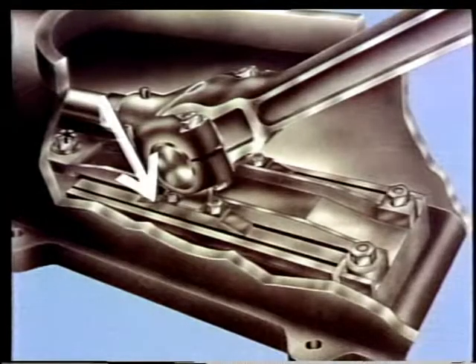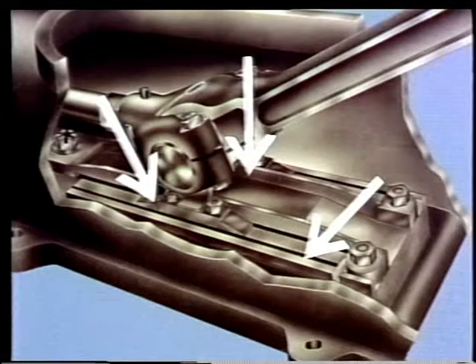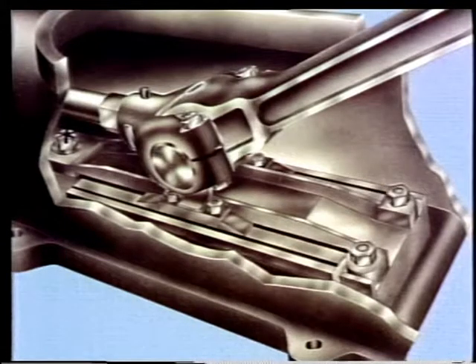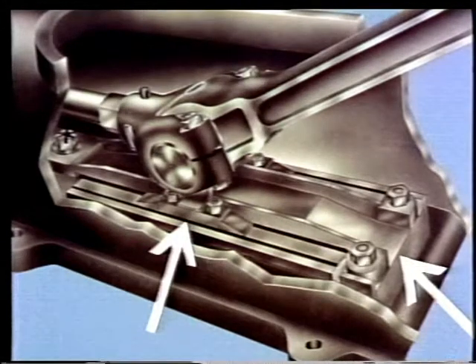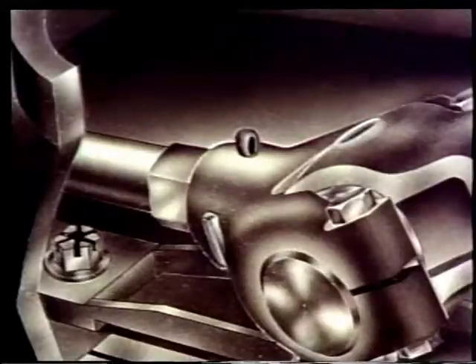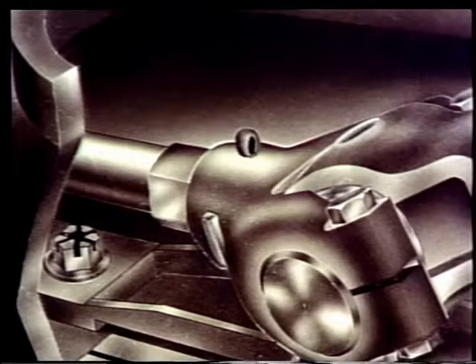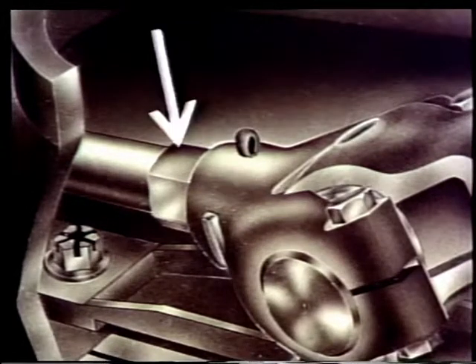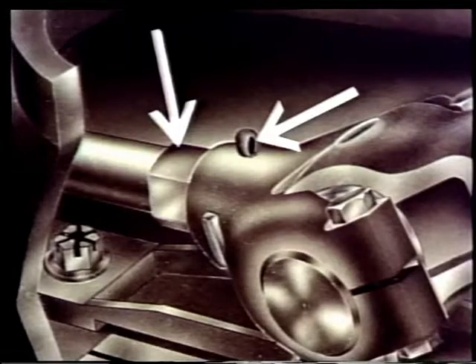This crosshead has a wear shoe and a top and bottom guide. The wearing shoe and top guide have a shim adjustment to take up for wear while maintaining the alignment of the piston rod. The piston rod is screwed into the crosshead and held there by a lock nut and cotter pin.